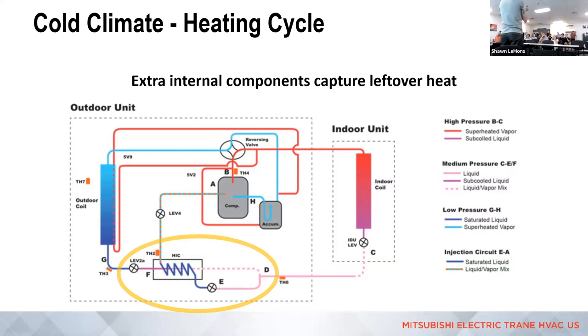It's now capturing the leftover heat as that refrigerant comes back through the cycle. So it's splitting the remaining vapor refrigerant from the liquid refrigerant, and using the liquid refrigerant to cool off the vapor refrigerant a little further. We capture that remaining phase change out of that refrigerant on its way back outside. That's one way we're capturing a bit more efficiency out of the system in an extremely cold environment. That's only on Hyperheat.